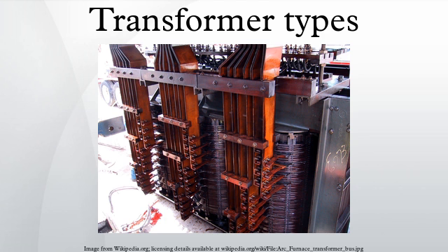Isolating transformer. An isolation transformer links two circuits magnetically, but provides no metallic conductive path between the circuits. An example application would be in the power supply for medical equipment, when it is necessary to prevent any leakage from the AC power system into devices connected to a patient. Special-purpose isolation transformers may include shielding to prevent coupling of electromagnetic noise between circuits, or may have reinforced insulation to withstand thousands of volts of potential difference between primary and secondary circuits.